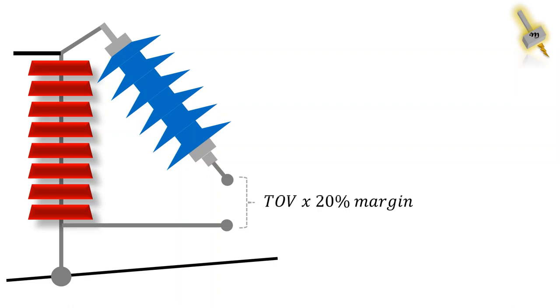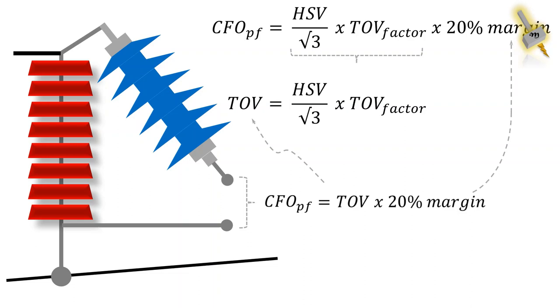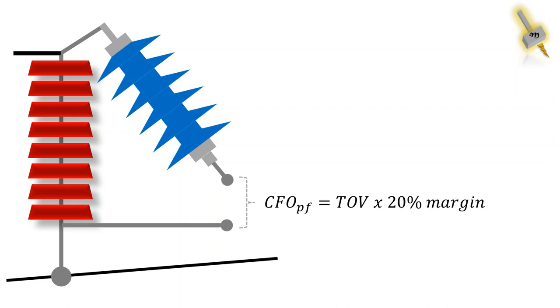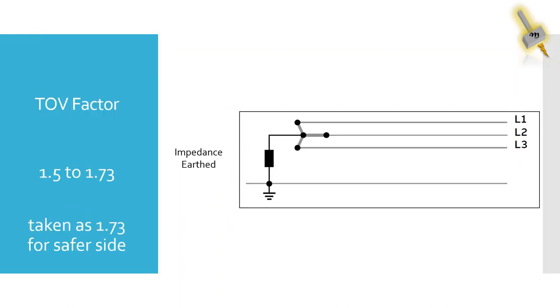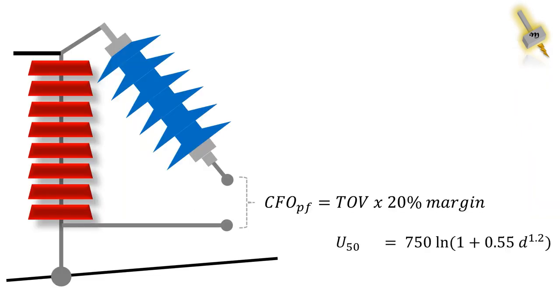Now we must find what is the minimum spark gap distance. The minimum spark gap distance is set to 20% higher than the maximum expected temporary over voltage of the system. This is the critical flashover voltage for power frequency level. Now the typical TOV factors are here. For getting the spark over voltage, another factor U50 or 50% flashover voltage is used. This factor considers rod plane spark gap. It can be termed as U50RP instead of just U50. The reason for using rod plane gap is it has the lowest withstand voltage compared to all other electrode configuration. Replace the U50RP with CFO and rearranging the equation gives us the minimum spark gap distance.